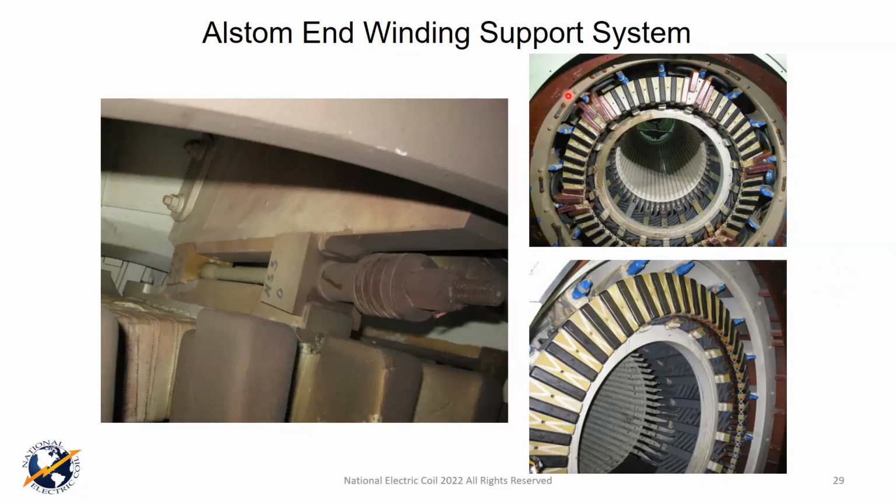There are a lot of things. We could spend a lot of time talking about it, but the design of those, I think Alstom and ABB referred to them as lugs, okay? And there were a number of bulletins put out on some of the smaller ABBs and also on the larger Alstom ones, and they had some pretty sharp geometries in the connectors themselves, the way they were blocked and the way they were held together. And there is some truth to the brazing.